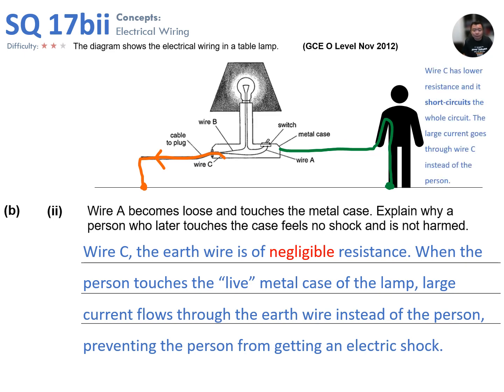Because wire C, the earthing wire, has a lower resistance than the human body, even when we touch the faulty appliance there will still be a short circuit. All the current will pass through the earthing wire, and no current will pass through the human. This is how an earthing wire protects the user from an electric shock when there's a fault within the circuit itself.